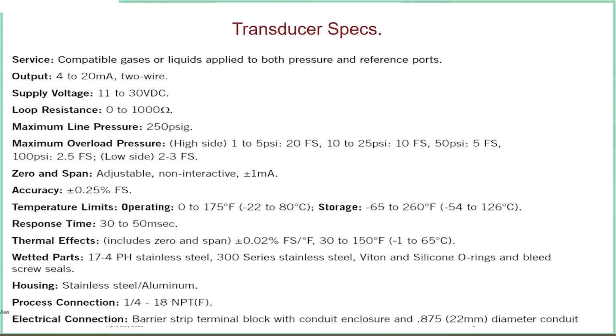Obviously, maximum overpressure is 250, so that wouldn't be a problem. There is a zero and span for the 4 to 20. You can adjust it plus or minus 1 milliamp. I don't think you'd ever have to do that, but it does have 2 pots in the top of the DP transducer, so if you ever did need to tweak that in, it could be done. And the accuracy is 0.25%.